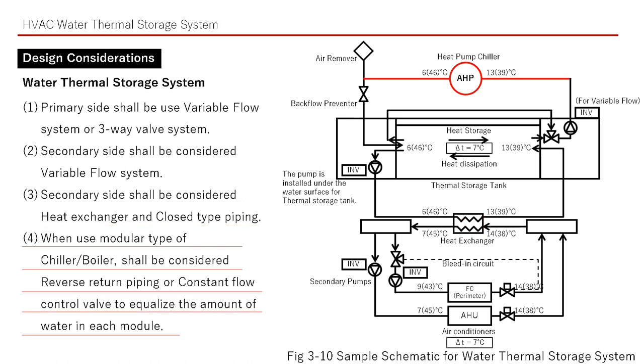When using a modular type of chiller or boiler, shall be considered reverse return piping or constant flow control valve to equalize the amount of water in each module.